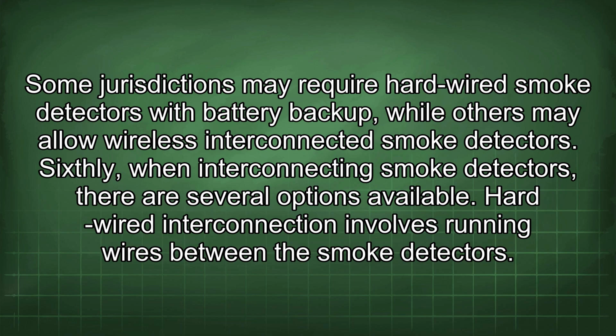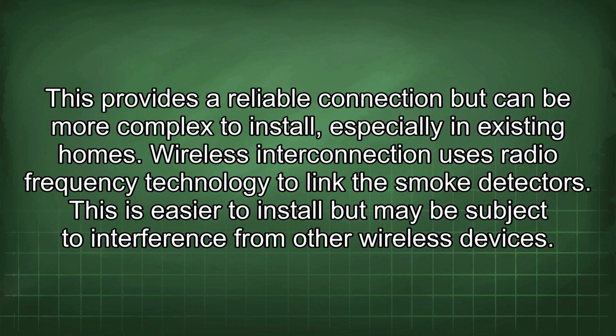Sixthly, when interconnecting smoke detectors, there are several options available. Hardwired interconnection involves running wires between the smoke detectors. This provides a reliable connection, but can be more complex to install, especially in existing homes. Wireless interconnection uses radio frequency technology to link the smoke detectors. This is easier to install, but may be subject to interference from other wireless devices.